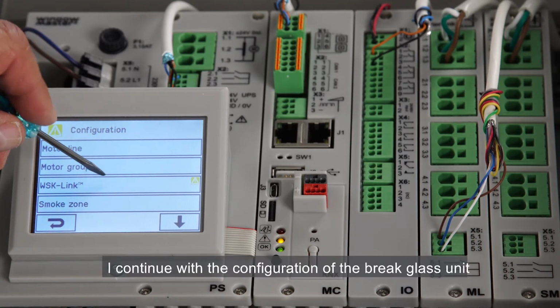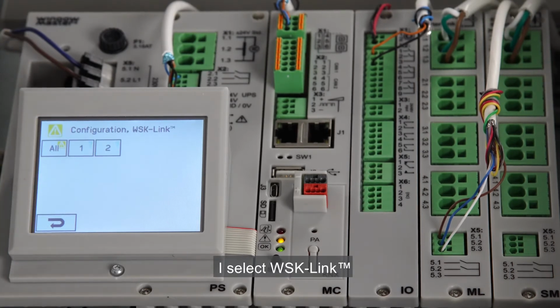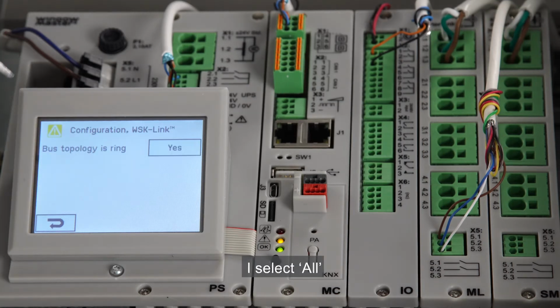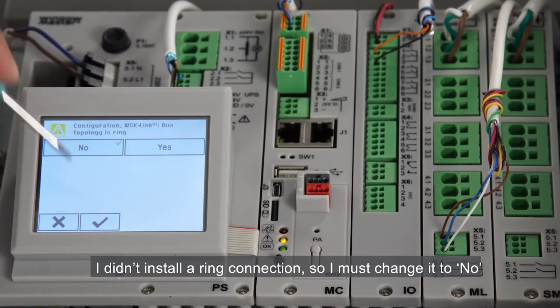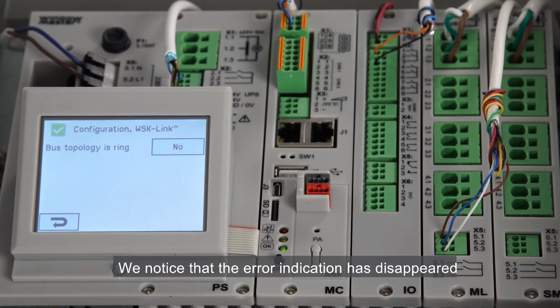I continue with the configuration of the break glass unit. I select WSK link. As you can see here, the panel already detected the 2 break glass units that I connected earlier. We see that there is an error indication at All. I select All and can see that the bus topology is by default set to ring. I didn't install a ring connection, so I must change it to No. We notice that the error indication has disappeared.